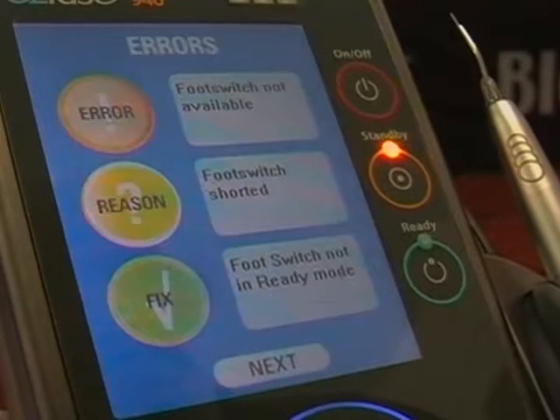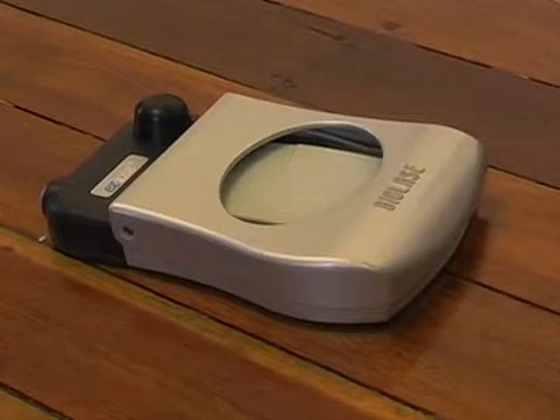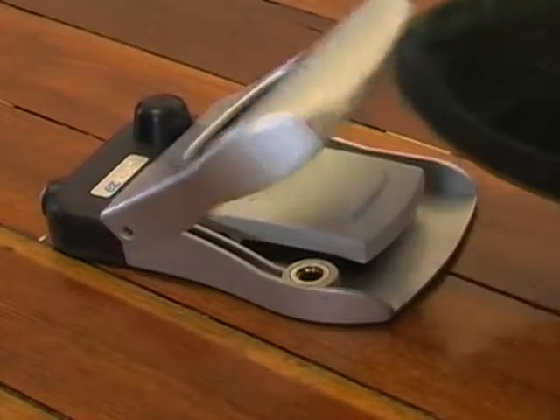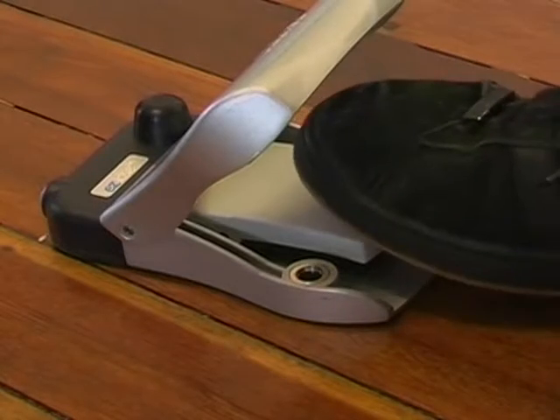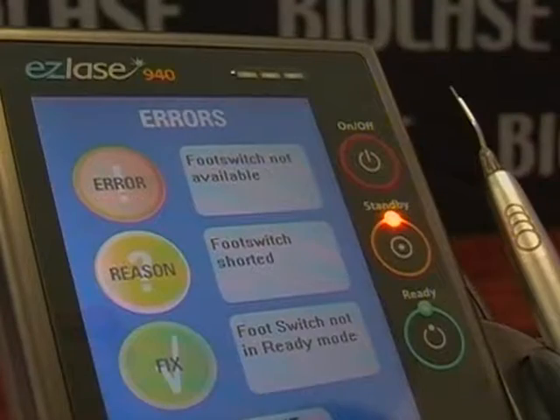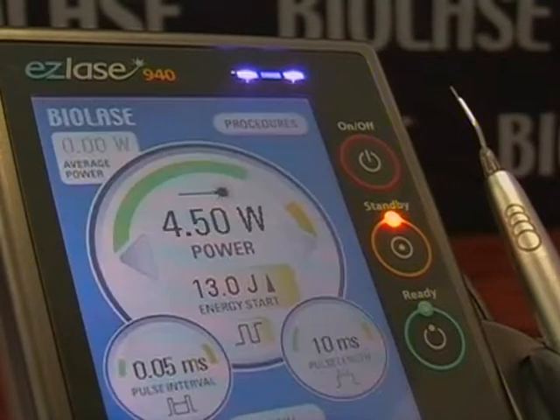Disconnect the cable from the Ezlase and also from the back of the foot pedal. The Ezlase will show this error message. Now, open up the foot pedal guard, depress the pedal switch and hold it down until the blue light at the top of the screen flashes and the error message goes away. The foot pedal is now operating wirelessly.